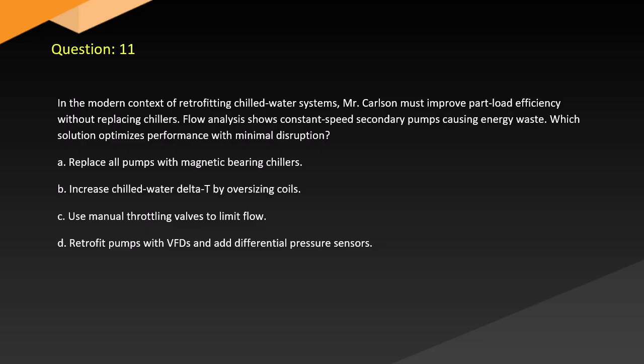Question 11. In a modern context of retrofitting chilled water systems, Carlson must improve part load efficiency without replacing chillers. Flow analysis shows constant speed secondary pumps causing energy waste. Which solution optimizes performance with minimal disruption? A. Replace all pumps with magnetic bearing chillers. B. Increase chilled water delta T by oversizing coils. C. Use manual throttling valves to limit flow. D. Retrofit pumps with VFDs and add differential pressure sensors.